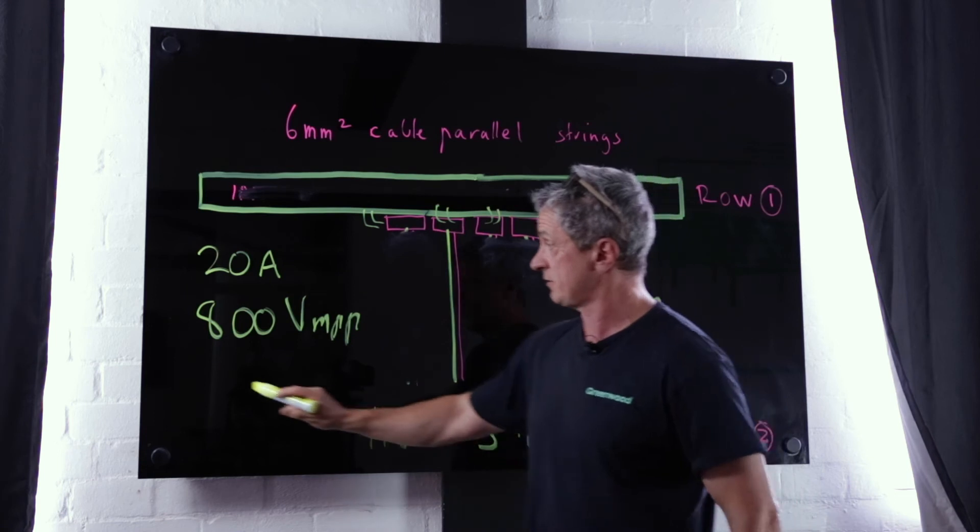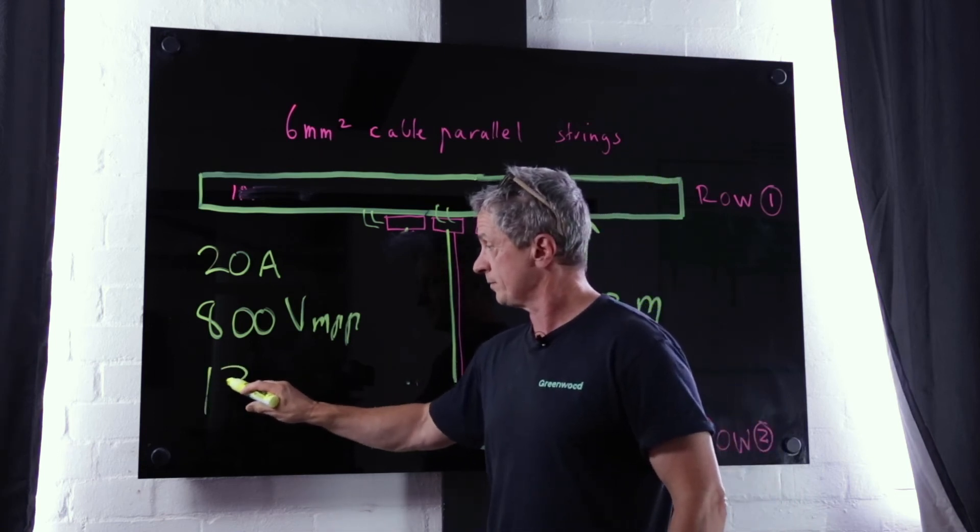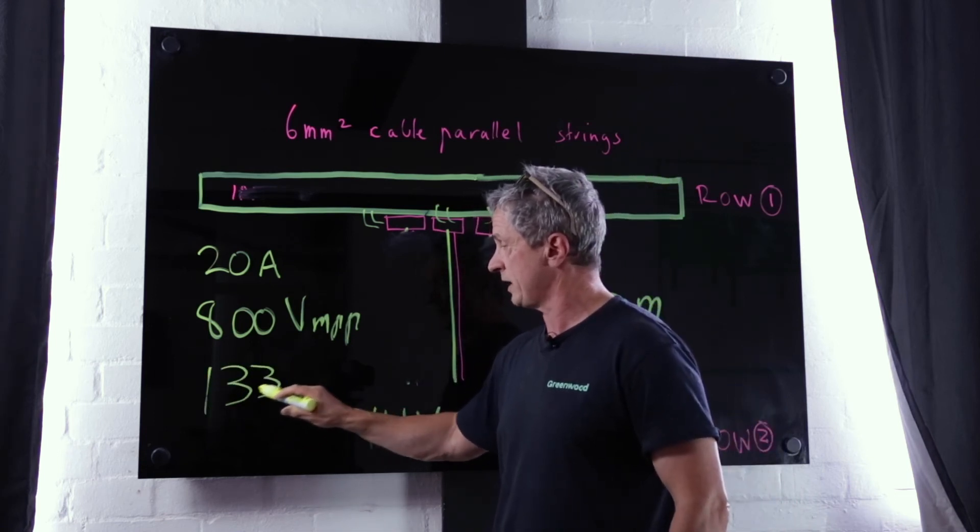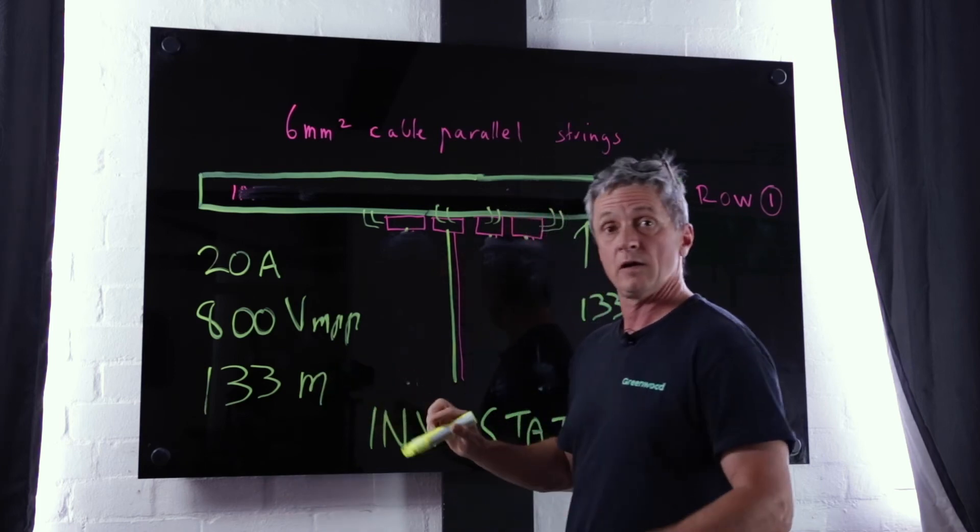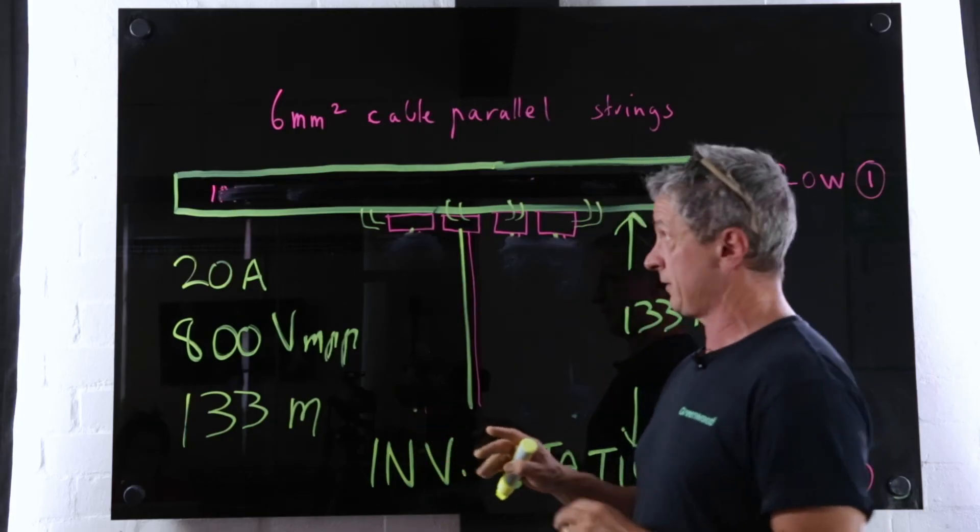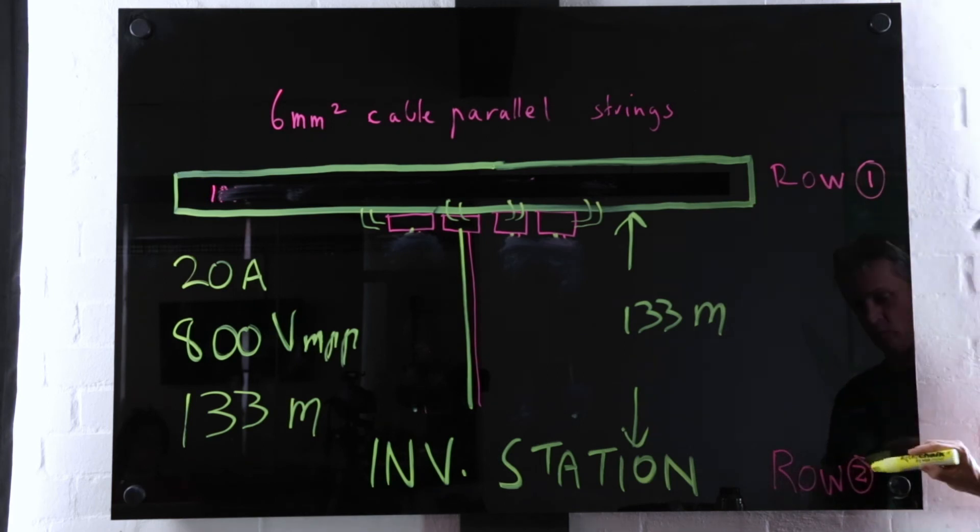That's row one all the way to row 20, not row two. So for 6mm parallel cable we're looking at a volt drop of 2.49% for the cable run holding 20 amps because it's two strings parallel over 133 meters.